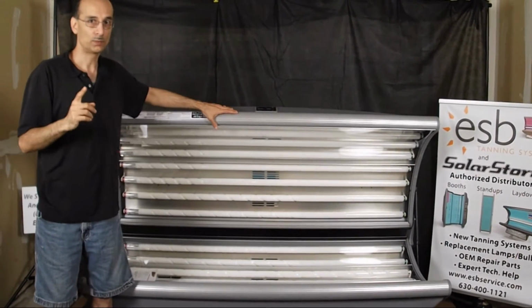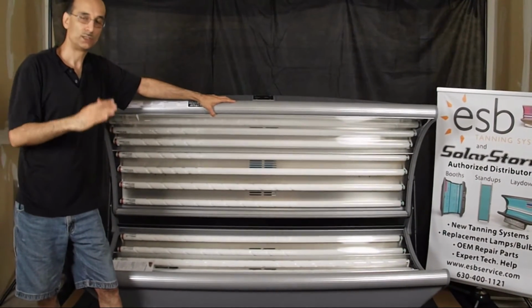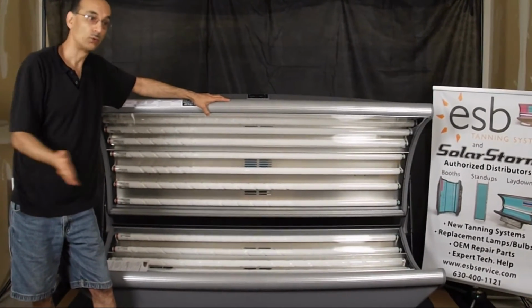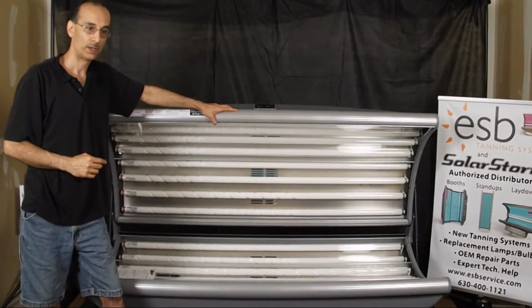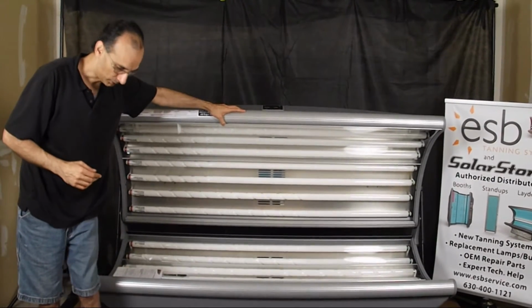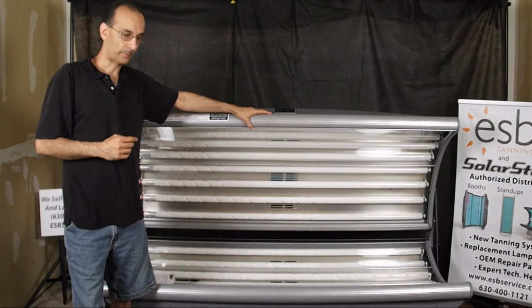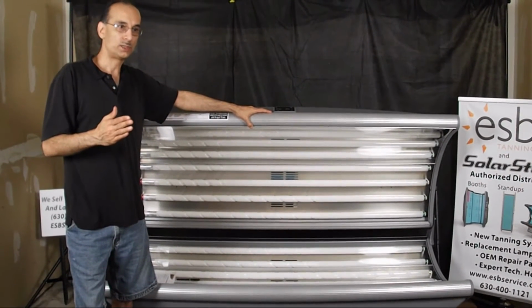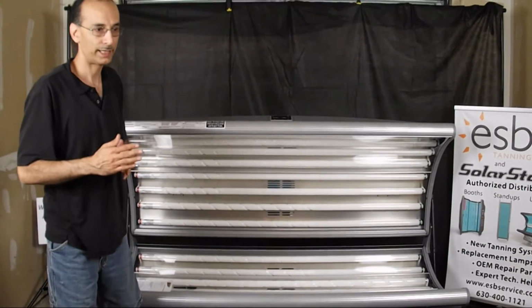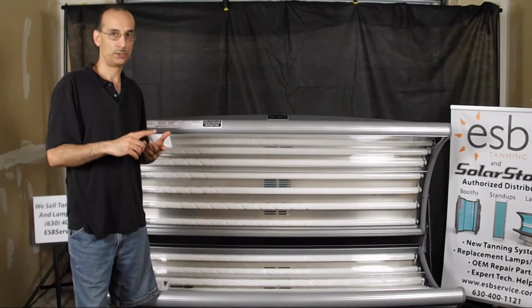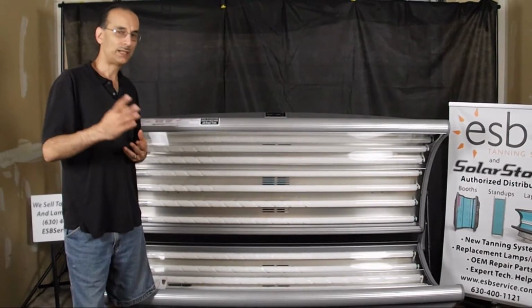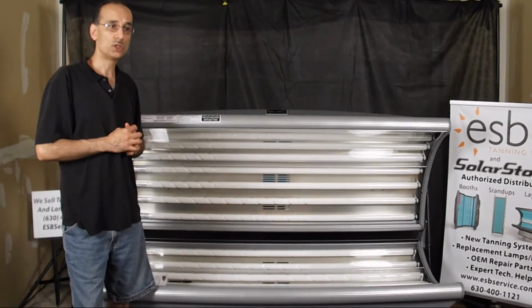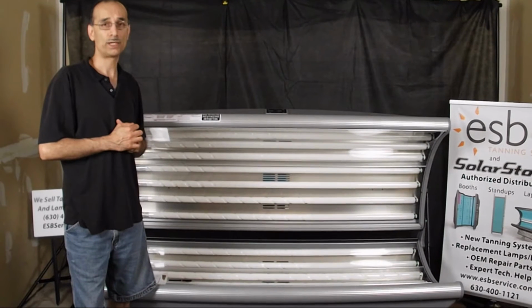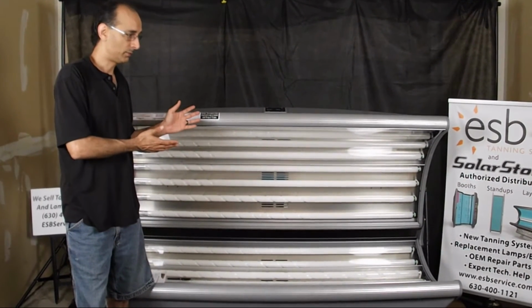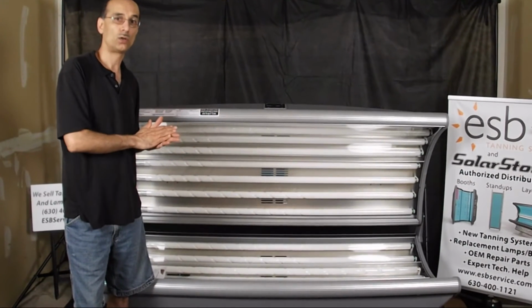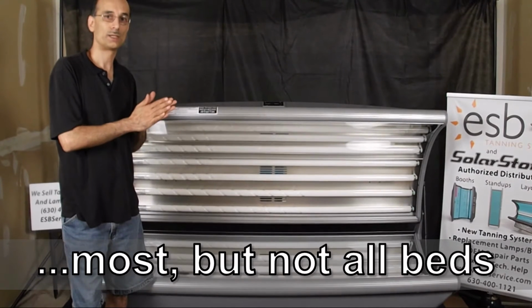You do not want to use a buck booster if your receptacle voltage is just fine for your bed, because then it's going to throw it out of the range that it needs to be in. So the next question that comes up is, well, what about a surge protector? Well, a surge protector is there only to protect the circuitry in the case of, say, a swell in the voltage or a spike in the voltage. The problem that I see with that is the fact that most surge protectors that are available are only rated for 15 amps. And everything that the tanning bed is plugged into, the whole electrical service needs to all be spec'd for 20 amps.